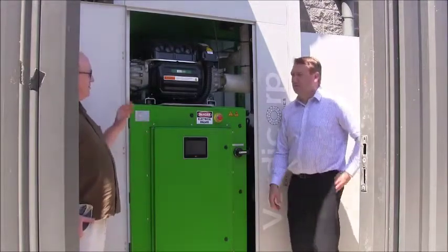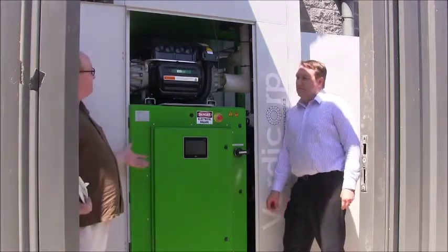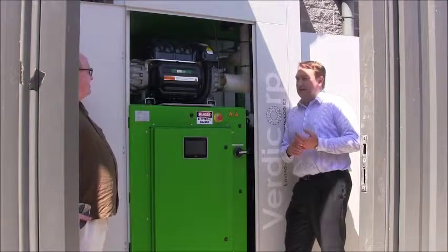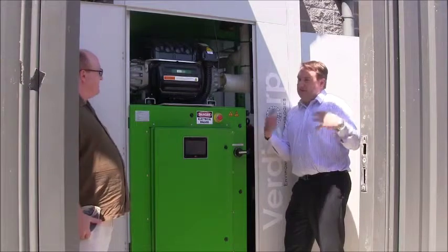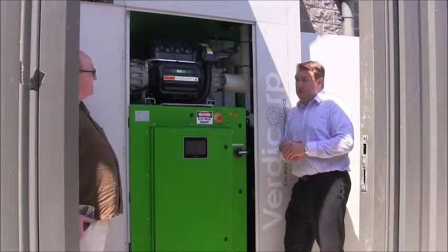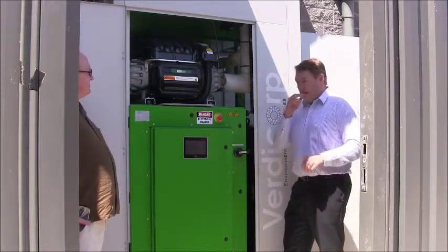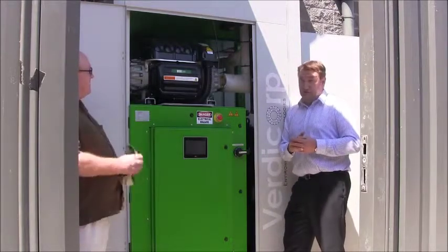What sort of customers are you looking at? People doing thermal mills, factories, steel mills, cement mills, hotels, resorts — anybody with a thermal load? Basically anywhere there's a thermal load, we can look at getting onto the back of it. We can take power off diesel and gas gensets — take all the energy out of the exhaust plus around 40 to 50 percent of the jacket water — and we can use that to drive these units. We can either make nominally 10 percent more power off a given genset, or reduce your fuel bill. On a diesel set, we might be able to achieve a 7 or 8 percent reduction in fuel bill.